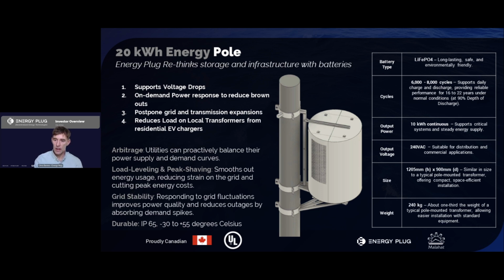And so a traditional transformer, some of them, I mean, they can be that large. What's good about ours, however, is the weight. It only comes in at about 240 kilograms. And so a similar size transformer is about three times the weight. So the poles are more than able to support these. And in fact, this pole-mounted unit can be installed in threes. So looking again very similar to what you'd expect to see from traditional transformers on utility poles.